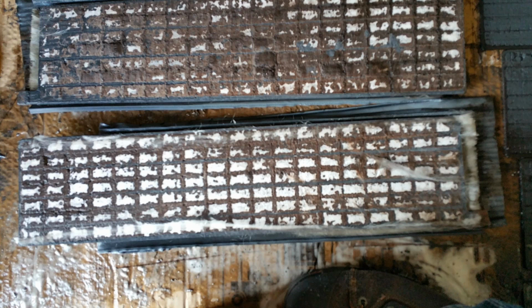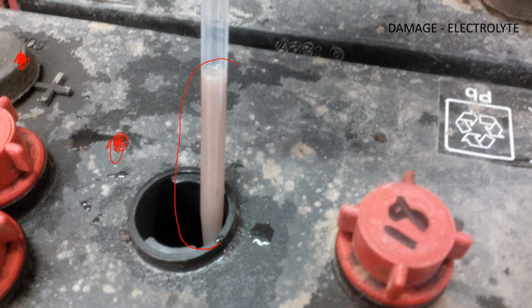So I take my positive lead and connect it to my positive post here, and I take my negative lead and put it right here on the top of the battery. I'm measuring positive to negative, and that voltmeter is telling me there's 0.2 volts here. There shouldn't be any voltage there.